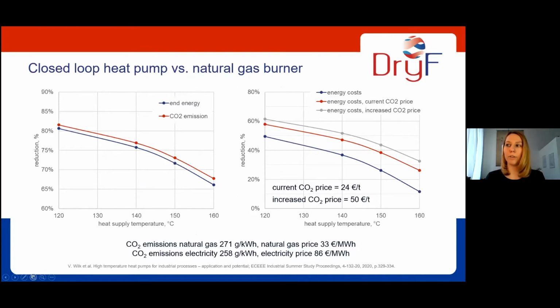On the left you see the reduction in end energy and CO2 emissions as a function of the heat supply temperature. We operated the heat pump ranging from 120 degrees C up to 160. At 120 degrees C, emission reduction and end energy consumption are reduced by 80%. If we increase the temperature, we need more electricity, but we still save more than 65% of the energy compared to a natural gas burner.